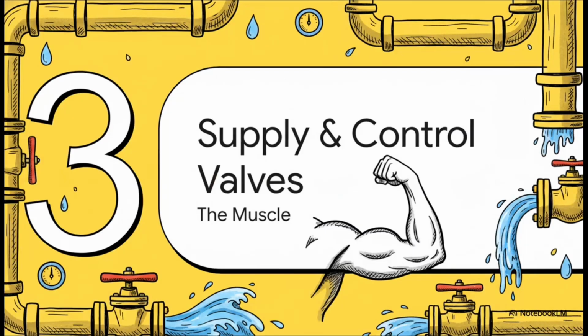Now, on the complete opposite end of the spectrum is a pre-action system. You'll see these in places like massive server rooms where an accidental water leak would literally ruin millions of dollars of equipment. It uses closed sprinklers and independent fire detection devices. It won't even let a drop of water into the piping network until a separate smoke or heat detector goes off first. Only then is it primed, and even then it still waits for an individual sprinkler head to shatter from the heat before releasing the water. It's an incredible failsafe. Let's move to Section 3, Supply and Control Valves, the muscle.